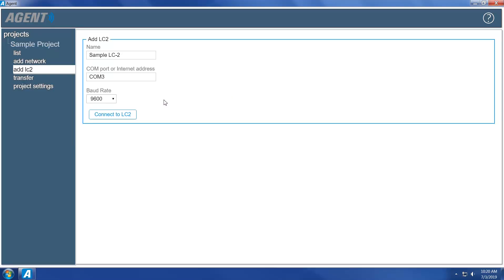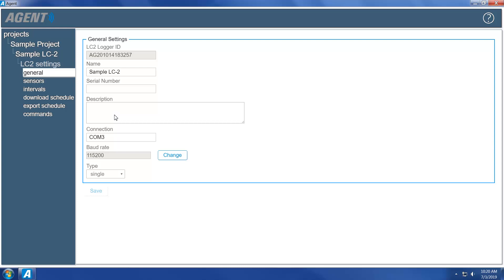The 9600 baud rate is the factory default setting and only needs to be changed if the user has set the LC2 to communicate at the alternative baud rate of 115200. After selecting a baud rate, click the Connect to LC2 button. Agent will attempt to connect to the data logger. Once the connection has been established, Agent will automatically navigate to a screen showing the general LC2 settings. Enter the serial number of the LC2 — this is recommended to differentiate one LC2 from another when there are multiple data loggers on one project. Enter a description if desired, then click Save.